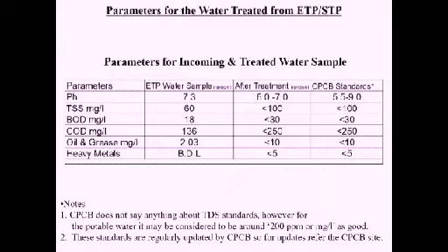Similarly, COD is chemical oxygen demand. In the untreated water, in an effluent treatment plant or sewage treatment plant, COD talks of lots of chemicals in the effluent or sewer water. And if it is less than 250, then it's considered that the majority of chemicals have precipitated or coagulated, turned into flocs, and there are no major chemicals making the water untreated or unhealthy, unhygienic.